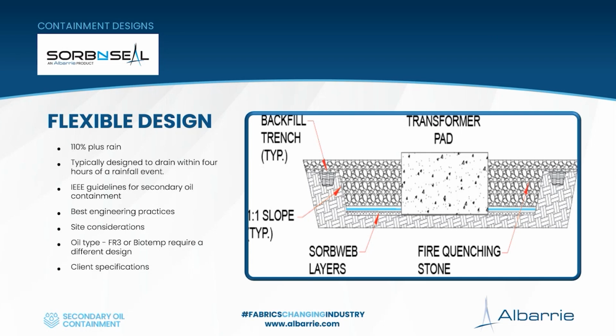Traditionally, we follow the IEEE guidelines for secondary containment, which call for 110% of the oil volume plus a 1-in-25-year rainfall event. Every client is different, so you may have your own standards you want to follow—just tell us what they are and we will follow them. We have customers ranging from 110% of the oil volume with no rainfall contained, to draining a specific amount of rainfall within a 4-hour period, to incorporating a 1-in-50 or 1-in-100-year rainfall event, or sometimes only containing 30% of the volume. These are all flexible parameters—you tell us which standard you want to follow, and we give you the best recommendation, but ultimately it's your decision.